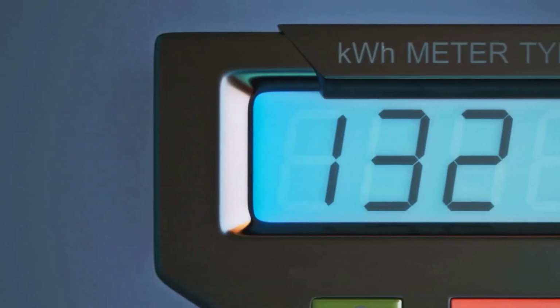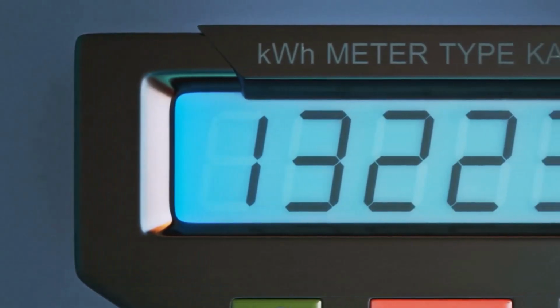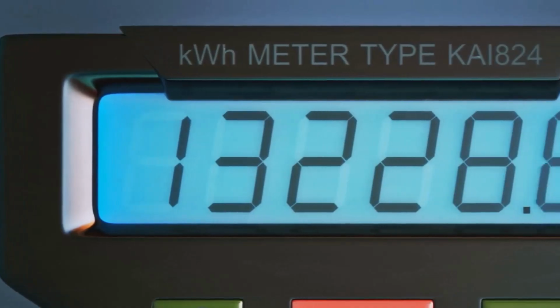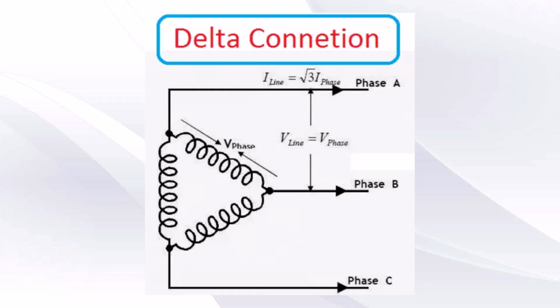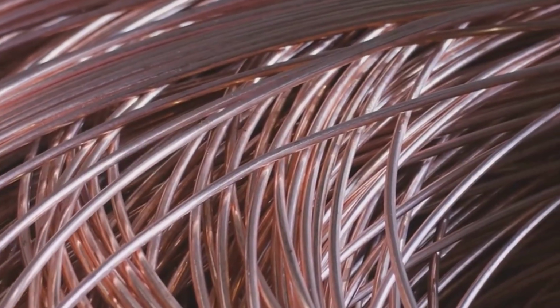Another drawback is the higher line current we talked about earlier. IL equals the square root of 3 times IP. Because the line current is 1.732 times greater than the phase current for the same amount of power, the conductors used for the lines need to be thicker and more robust. This can increase the cost of the wires.